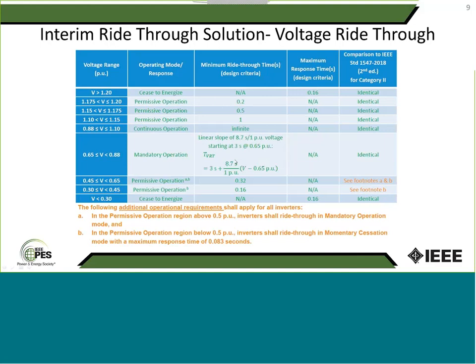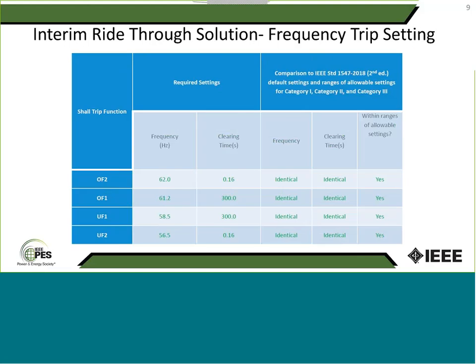I'm not going to walk you through every single line on this table. The whole point was, based on the processes, talk to your distribution protection engineers, make sure that they're comfortable with the required ride-through settings and capabilities, and then come to 1547 and pick the right category that offers those capabilities plus the trip settings. That's basically the process. The key here is to make sure distribution protection engineers are comfortable with what your regional ISO is proposing for the ride-through settings, especially the trip settings. Okay, because the capability is good to have, but really protection folks are concerned about the trip settings. So we make sure that both parties are talking and coordinating these settings. Okay, so that's done with voltage ride-through.